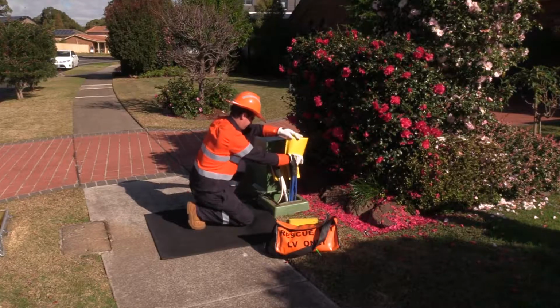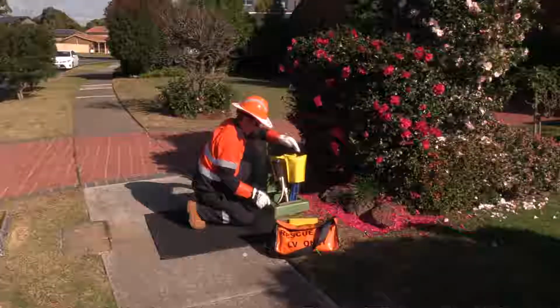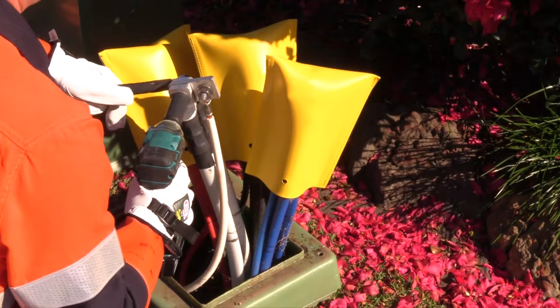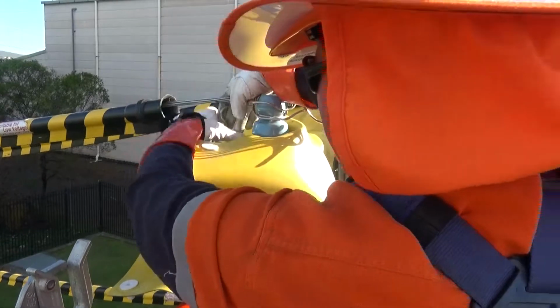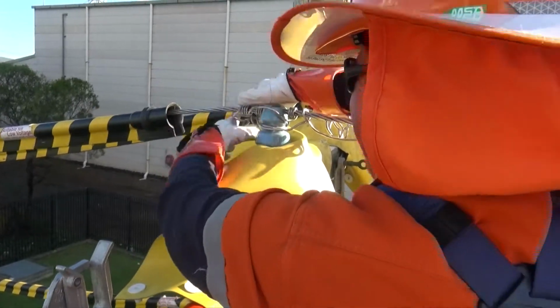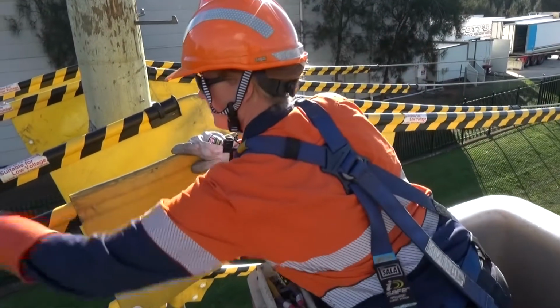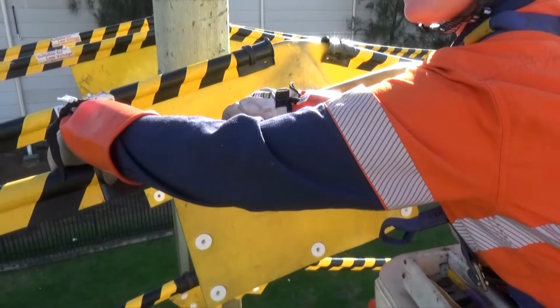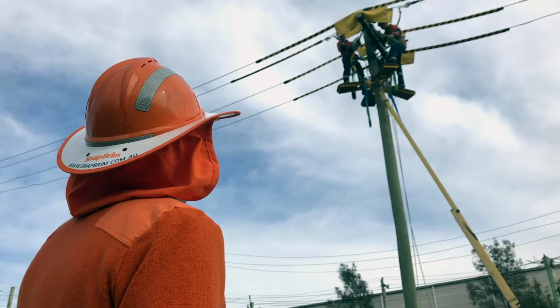The modification or replacement of energised components, the moving of conductors, and the installation or removal of conductors from live low voltage enclosures are higher risk tasks, and workers require additional live low voltage work authorisation to perform this type of work.